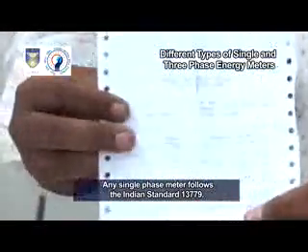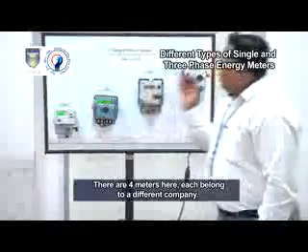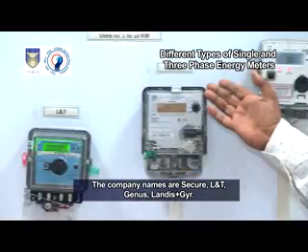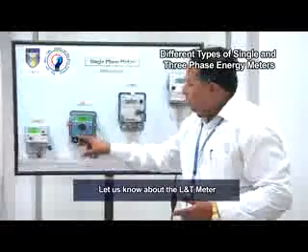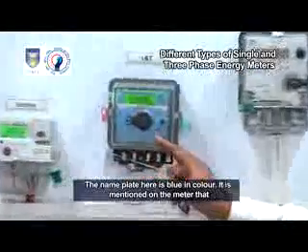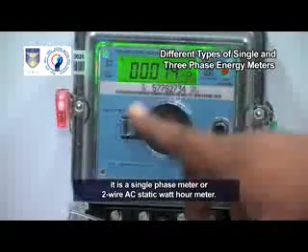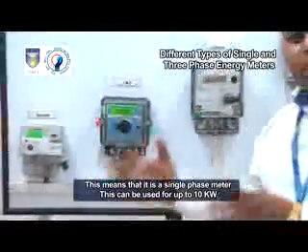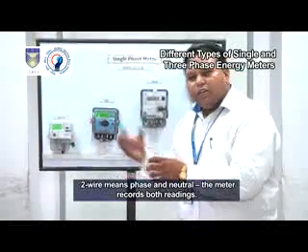Any single-phase meter follows the Indian standard IS 13779. There are four meters here, each belonging to a different company: Secure, L&T, Genus, and Landis and Gyr. Let us look at the L&T meter. The nameplate is blue in color and states it is a single-phase two-wire AC-static watt-hour meter, meaning no component is revolving. This can be used for up to 10 kW. Two-wire means phase and neutral, and the meter records both readings.